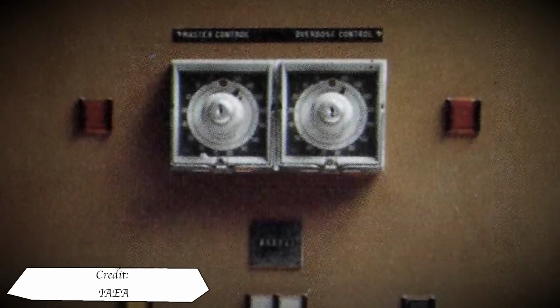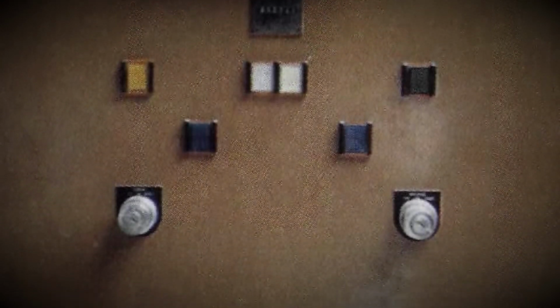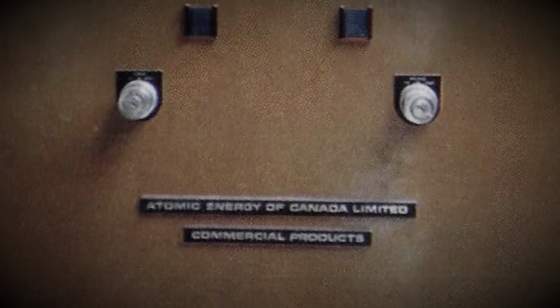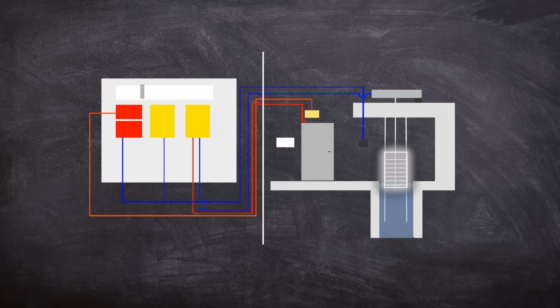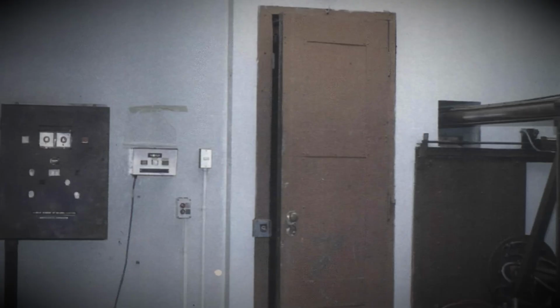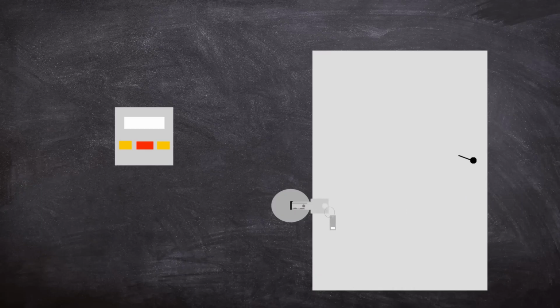The situation wouldn't get much better throughout the 1980s, with the facility making do amending the machinery, including modifications that the manufacturer would never have approved of. The lack of maintenance resulted in the vital monitor probe failing. In order to keep using the irradiator, it was removed, but you might wonder how the operators would gain access to the irradiation room. Well, a neat little trick was discovered.